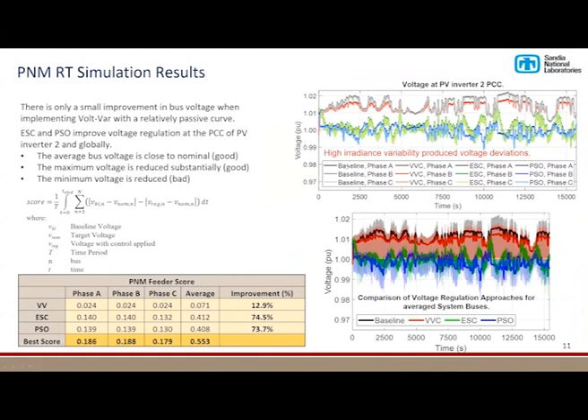And we ran the cases for a few different runs. So running baseline volt-var curve, extremum seeking control, and particle swarm optimization for each of the phases that's shown up here. But I'll focus your attention on the lower image. And so you see a large line running down this plot, which represents the average bus voltage for the entire feeder. And then you see multiple patches here, but the patch represents at the upper side the maximum bus voltage, and it stretches down to a lower point, which is the minimum bus voltage.